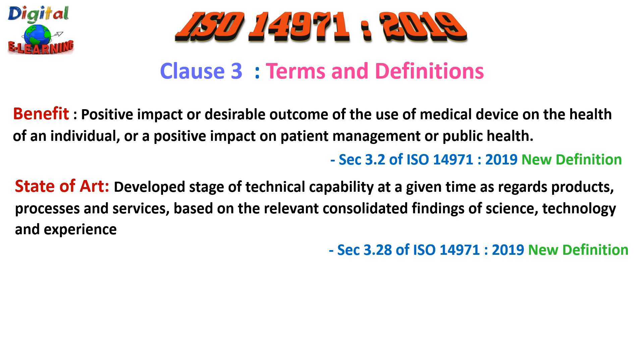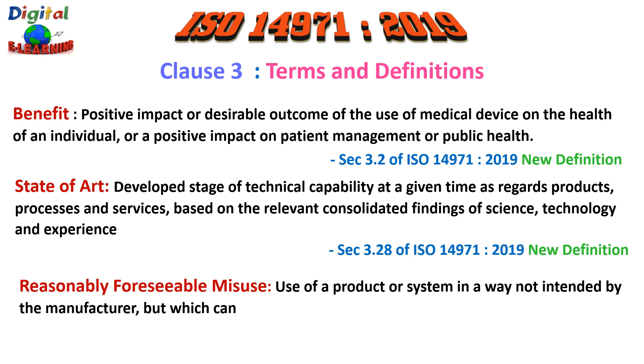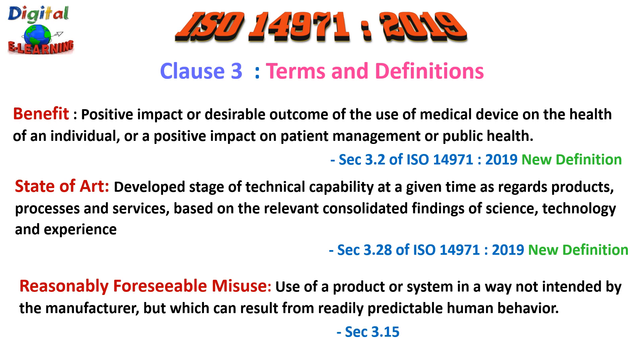The third new definition added is 'reasonably foreseeable misuse,' defined as the use of a product or system in a way not intended by the manufacturer, but which can result from readily predictable human behavior. All three terms — benefit, state of the art, and reasonably foreseeable misuse — have been added in the revised 2019 edition.